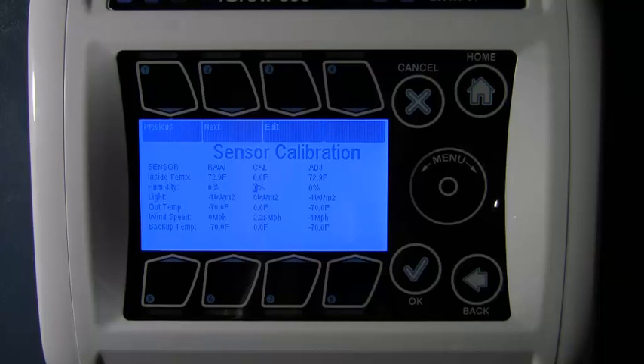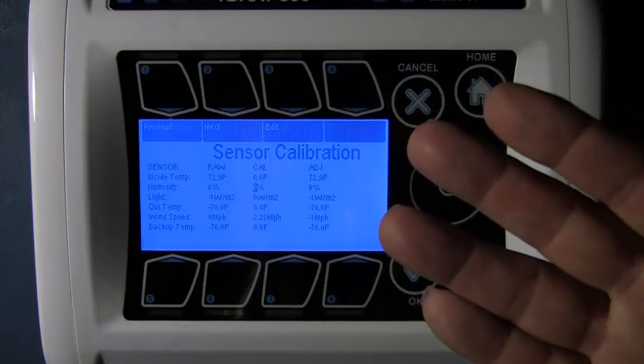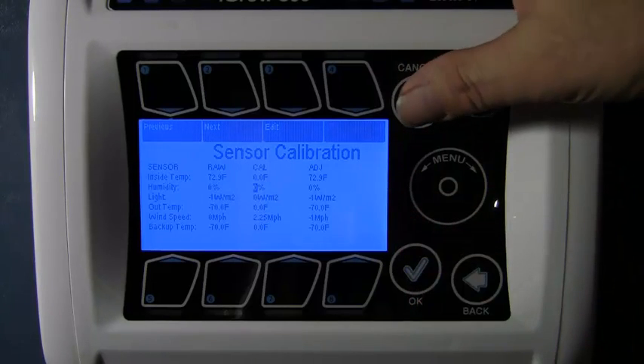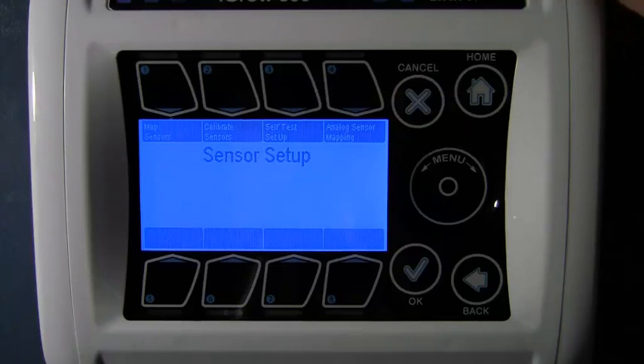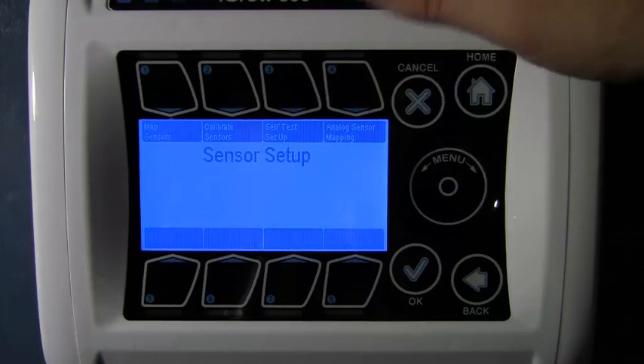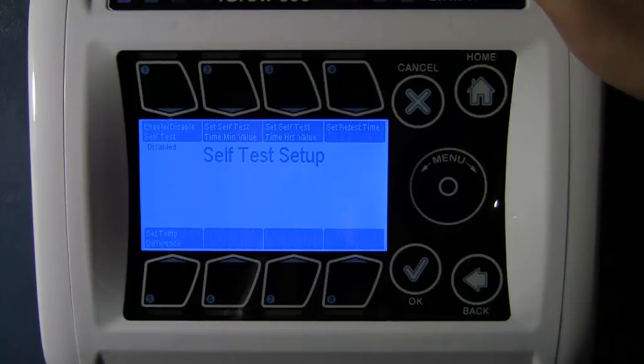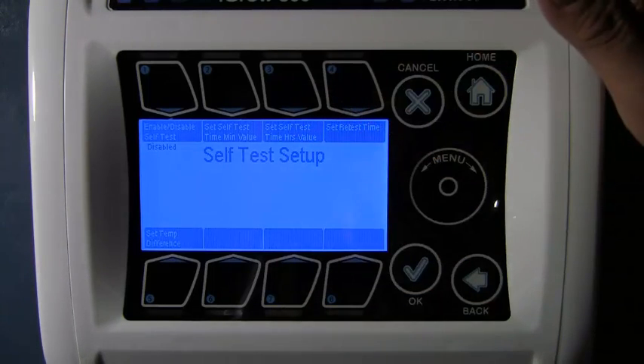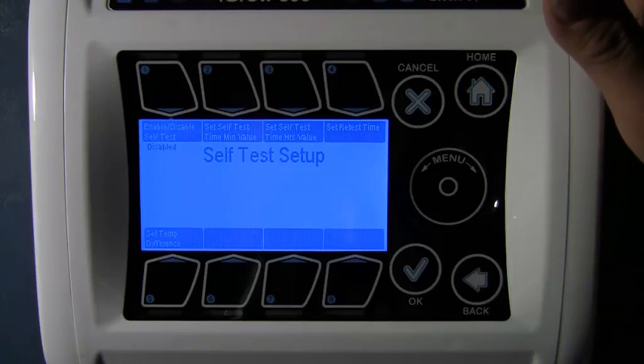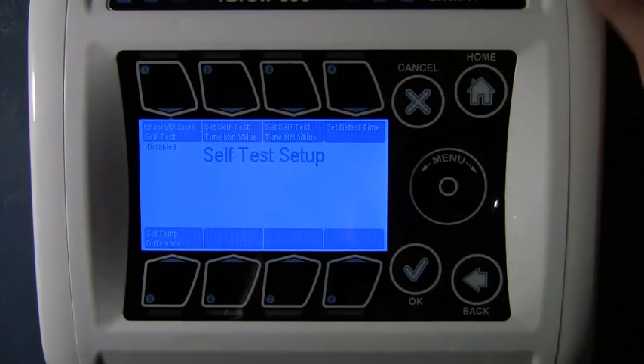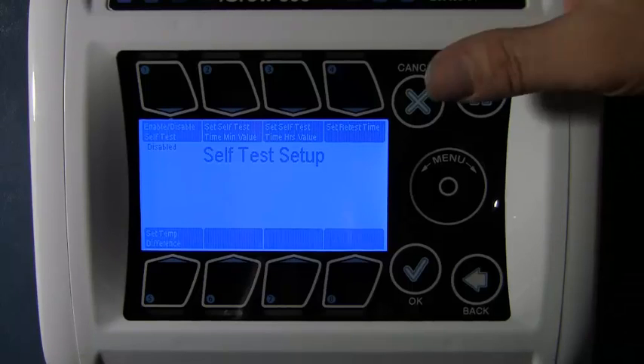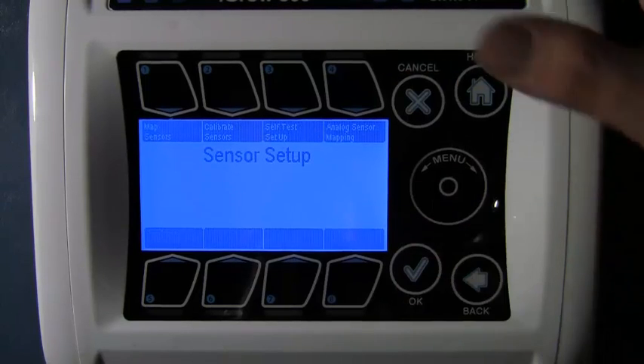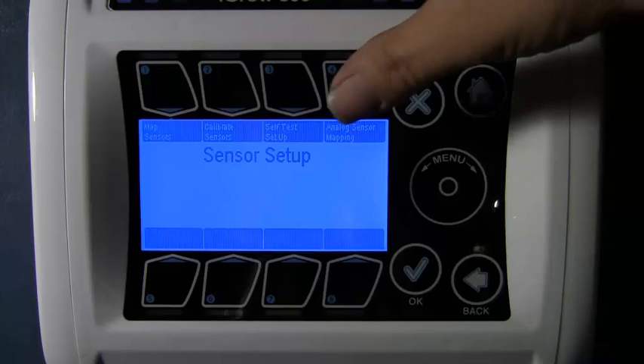Now that we have viewed the Calibrate Sensor option, let's go ahead and back out of this by hitting Cancel, and we'll go ahead and go into the Self-Test Setup. Now, on the sensor self-test, unless you are equipped with a backup sensor, this feature should be disabled. But if you have a backup sensor, this is where you would do your testing. And finally, we have analog sensor mapping.